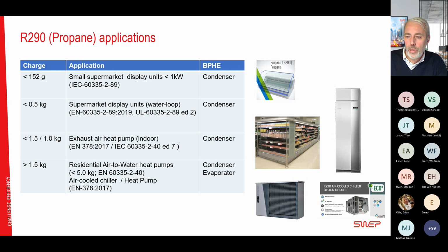Then we also see larger air-cooled chillers, and these typically have a charge of propane above 5 kilos, and they are governed by 378. And typically they are placed in ventilated systems in restricted areas or machine rooms, which allow higher charge than in other systems.